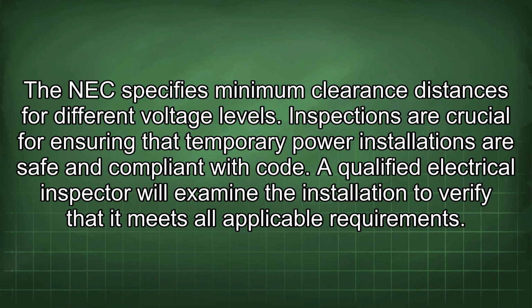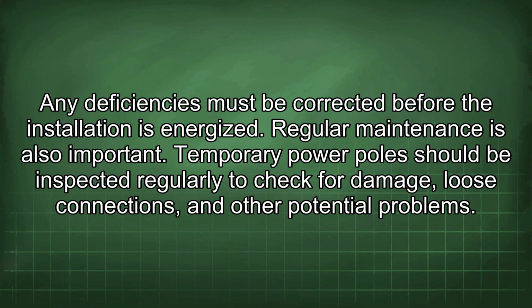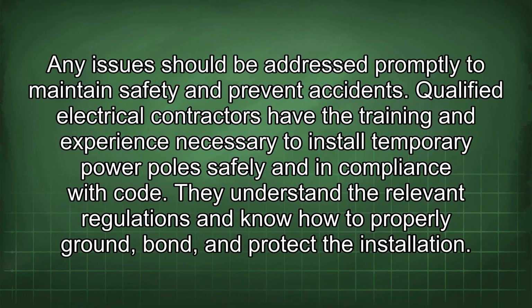Inspections are crucial for ensuring that temporary power installations are safe and compliant with code. A qualified electrical inspector will examine the installation to verify that it meets all applicable requirements. Any deficiencies must be corrected before the installation is energized. Regular maintenance is also important. Temporary power poles should be inspected regularly to check for damage, loose connections, and other potential problems. Any issues should be addressed promptly to maintain safety and prevent accidents.